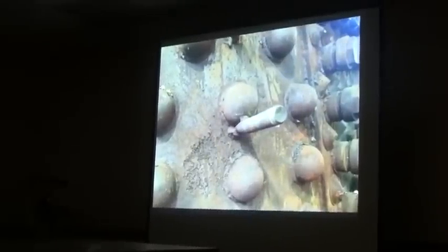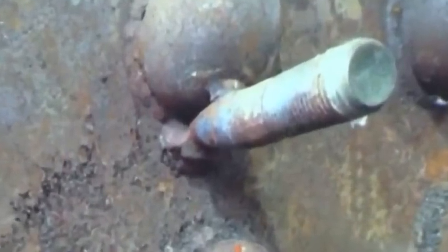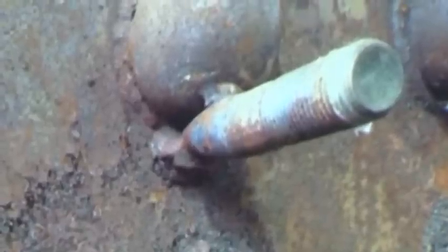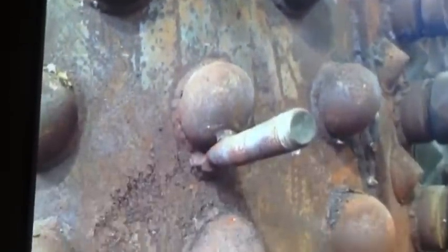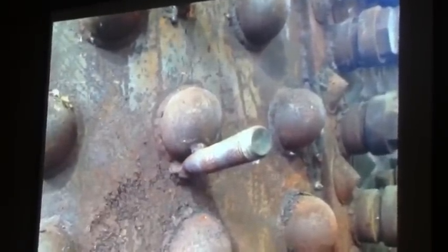And we've got more various things that we found, some studs and some bolts welded to the side of the boiler. You can see right above here, that's a remnant of a weld with a bolt welded to the boiler. And that bolt holds something. So that weld, it's not much of a weld, but it still needs to be more secure, and it shouldn't be located adjacent to that cap there.